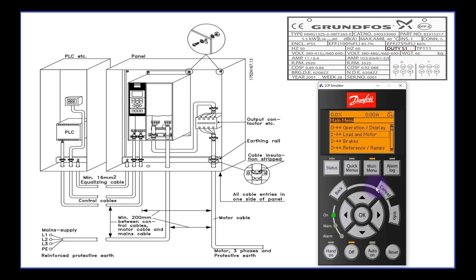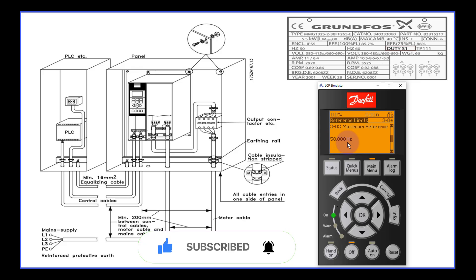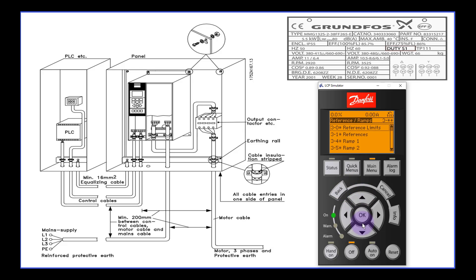The third step is to change the reference. Press OK, then select 'reference limit.' For minimum reference, depending on your process requirement, you can set the minimum and maximum reference limit. I will set minimum to 0 Hz. Then press the down arrow key and change the maximum reference — I want 50 Hz, so I press OK and key in 50 Hz. Once done, press the back button. Then go to 'references' and press OK to select it.